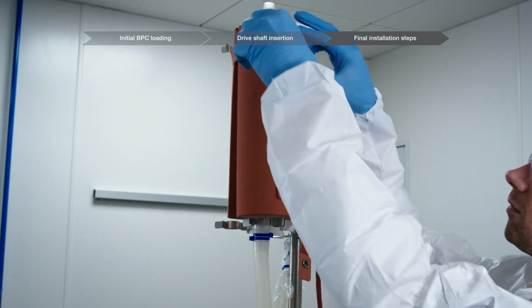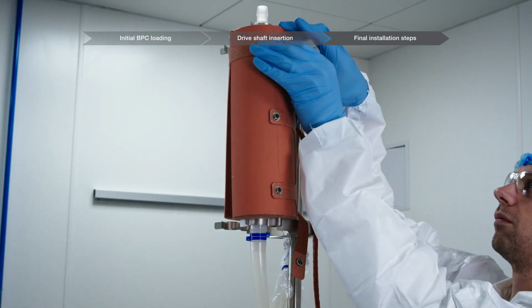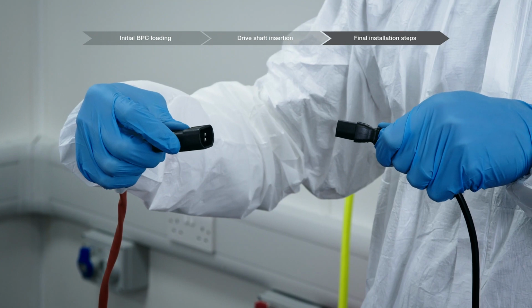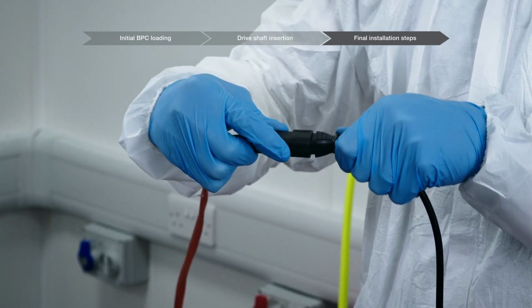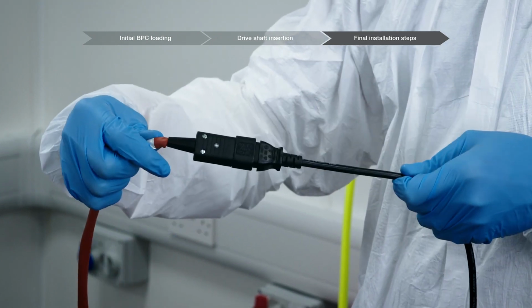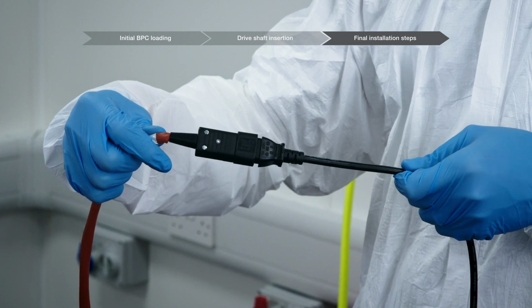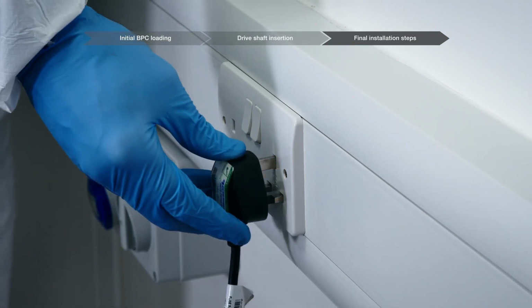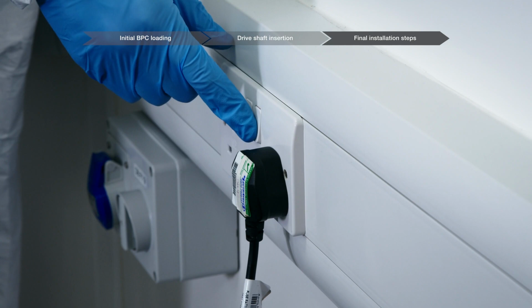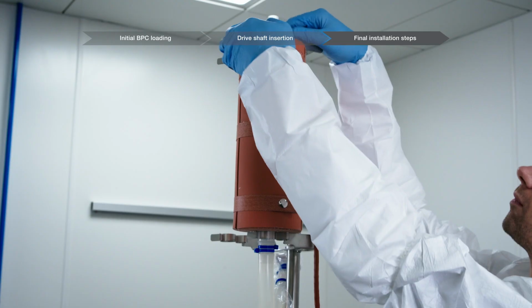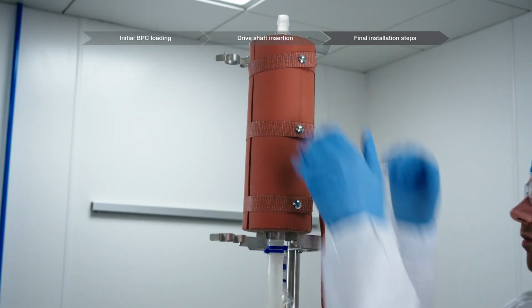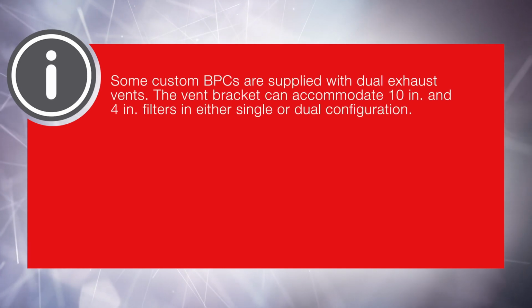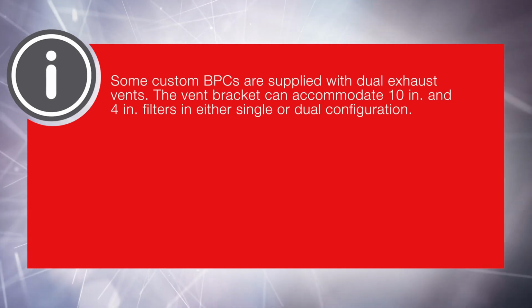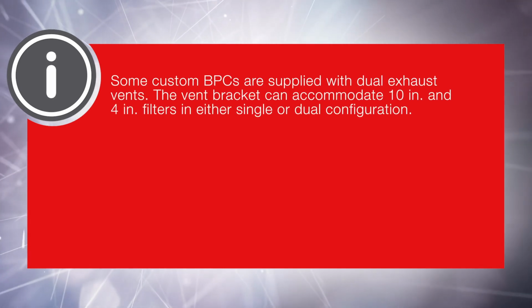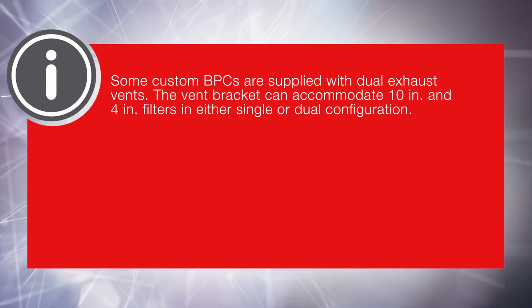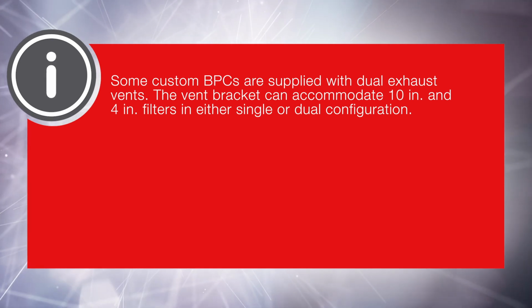Optional: wrap and secure the vent filter heater on the exhaust filter. Connect the power cord to the controller, which is preset to 50 degrees Celsius or 122 degrees Fahrenheit. Verify that the heater is plugged into an appropriate 120 or 240 VAC outlet. Ensure the exhaust vent filter is on its holder. Some custom BPCs are supplied with dual exhaust vents. The vent bracket can accommodate 10-inch and 4-inch filters in either single or dual configuration.